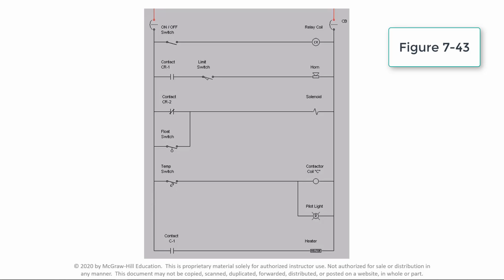Relay coil CR is energized when the on-off switch is closed and acts to close the CR-1 contact and open the CR-2 contact. For the horn to be energized and sound, both the CR-1 contact and the limit switch must be closed. The solenoid is energized and operates whenever the CR-2 contact or the float switch is closed.